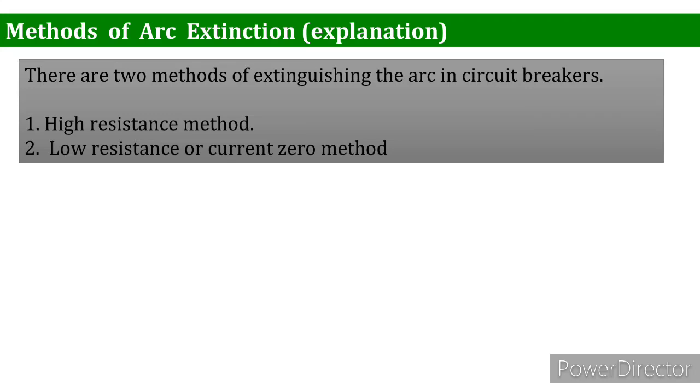So it also has some factors. You can see the deionization of the medium is the major key thing in this method, and you can deionize the medium by four methods. First, lengthening the gap. The dielectric strength of the medium, as we know, is proportional to the length of the gap between the contacts. Similarly, high pressure.